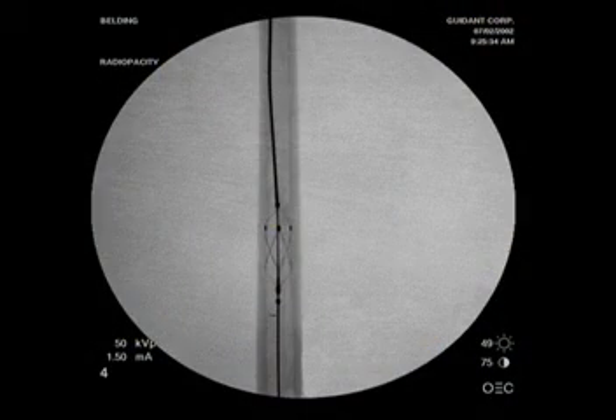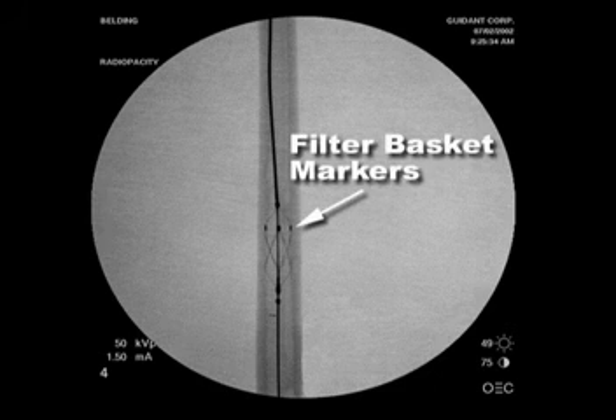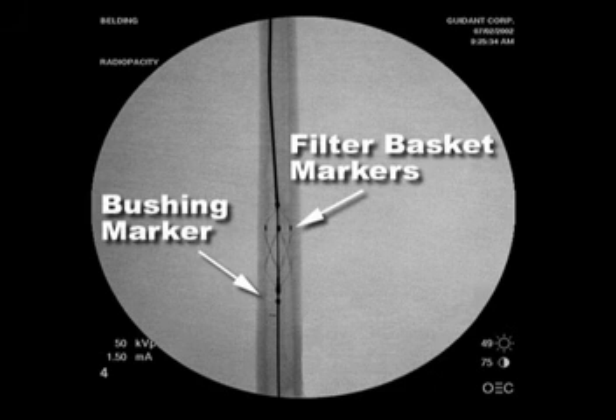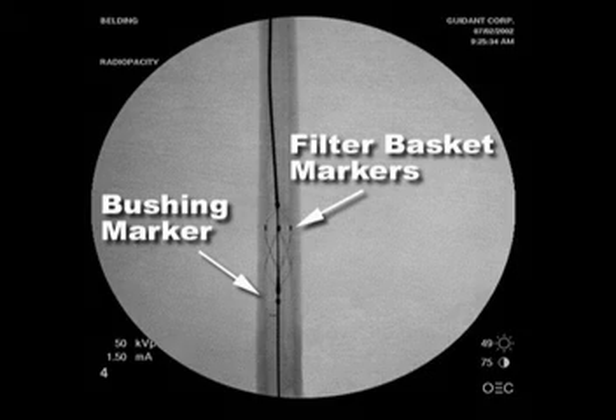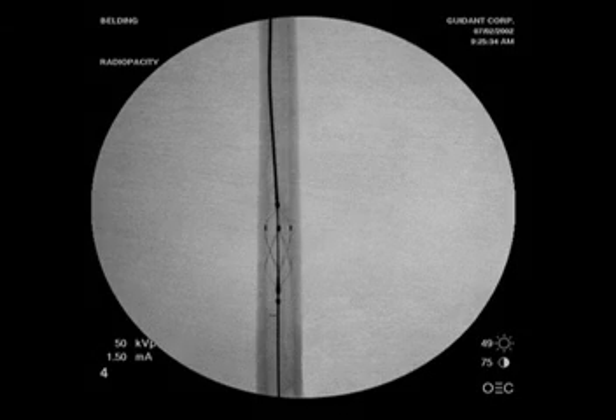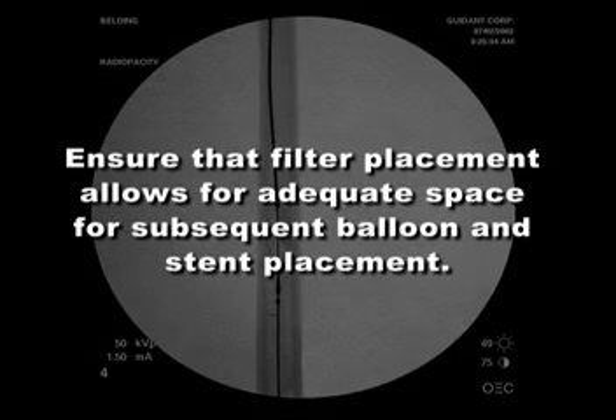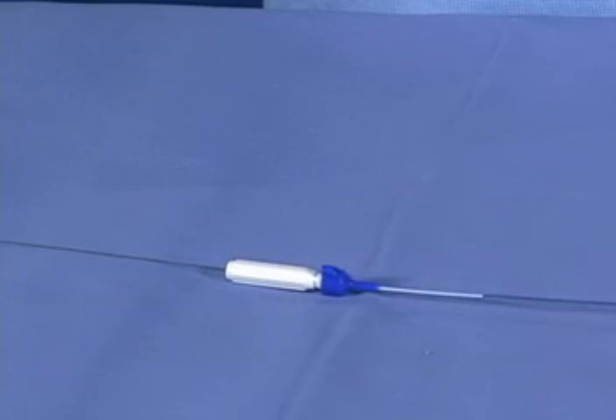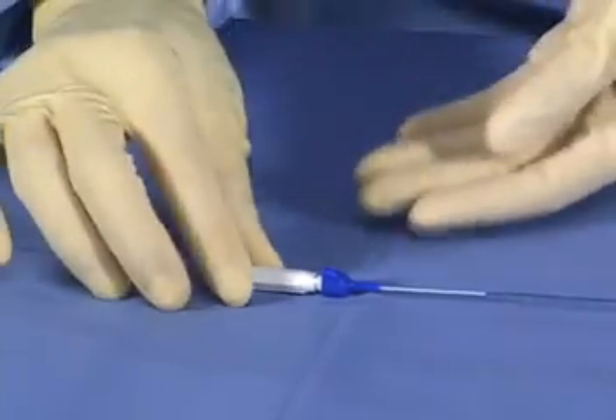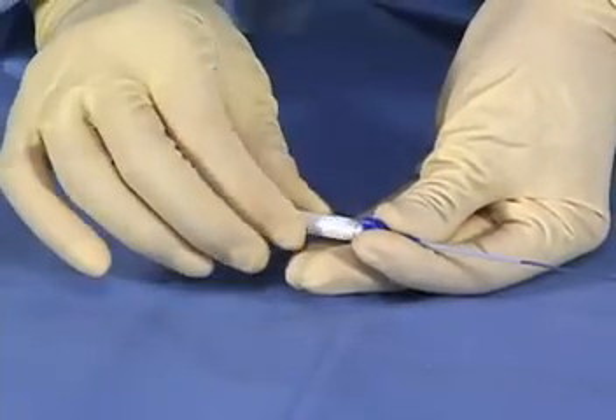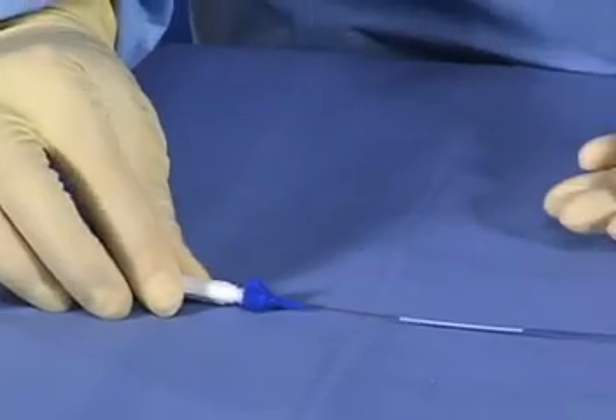Using the radiopaque guide wire tip, 4 filter basket markers, and the proximal bushing for reference, position the delivery system so that the filter basket is distal to the target lesion and will not interfere with the devices to be used for lesion intervention. Ensure that filter placement allows for adequate space for subsequent balloon and stent placement. Once the delivery system is in the desired position, loosen the torque device to prepare the filter basket for deployment.